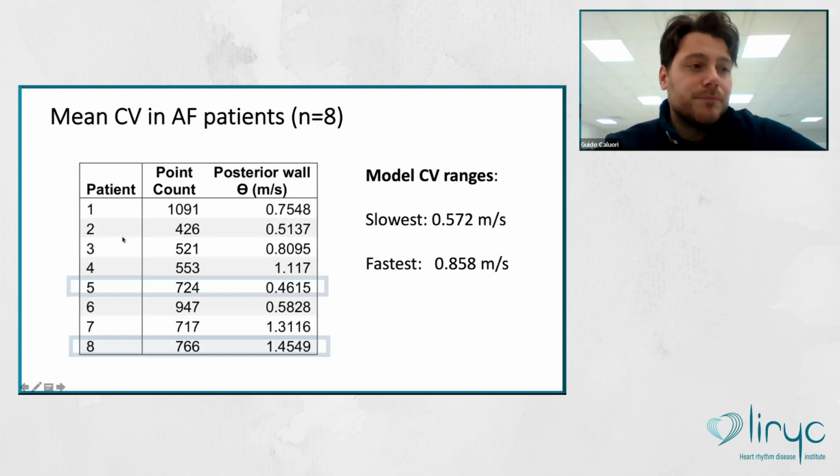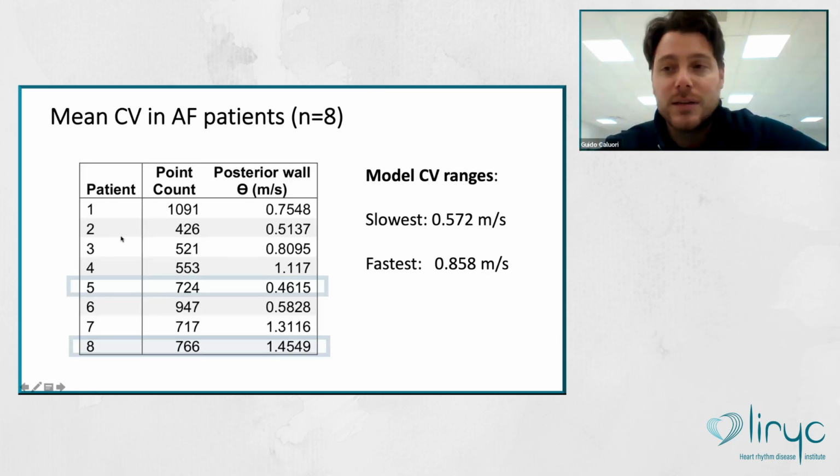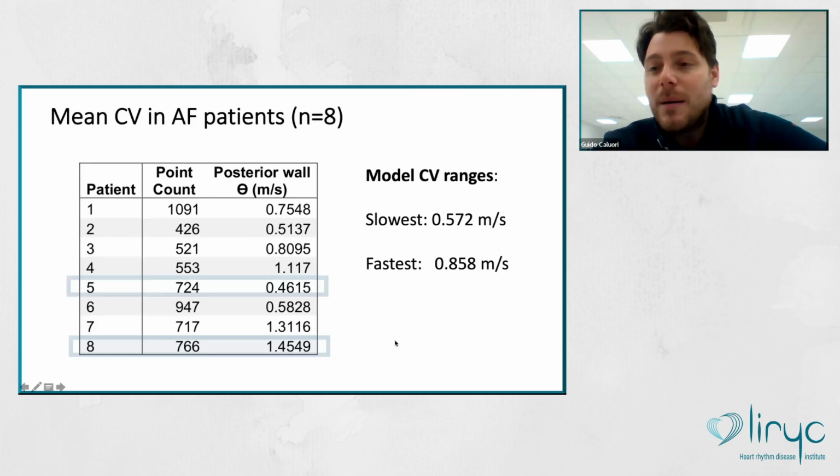If you trust raw data, right now what we're using is mostly the Rhythmia because of the high resolution and the fact that I have to clean, for example, 10% of the map. With the Carto, I risk cleaning 30%, 40% of the map sometimes.